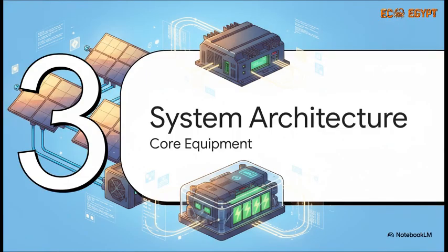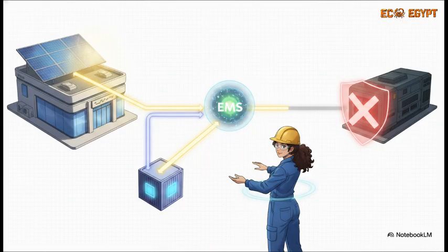All right, let's jump to Section 3, Core Equipment and Architecture. When you're completely cut off from the grid, your energy management system, the EMS, is basically the brain of the whole operation. And it follows this incredibly strict power priority sequence. The absolute top priority is using the PV generation. That free solar energy goes straight to the facility's load supply. If there's any left over, it charges the BESS. Only as an absolute last resort does the EMS fire up the diesel generator.